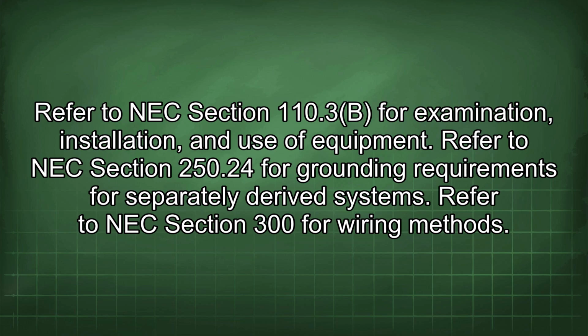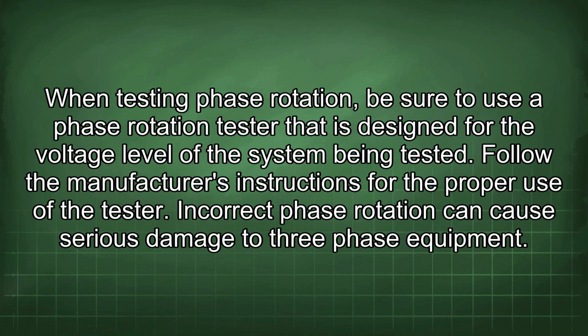Refer to NEC section 250.24 for grounding requirements for separately derived systems. Refer to NEC section 300 for wiring methods. When testing phase rotation, be sure to use a phase rotation tester that is designed for the voltage level of the system being tested. Follow the manufacturer's instructions for the proper use of the tester. Incorrect phase rotation can cause serious damage to three-phase equipment.